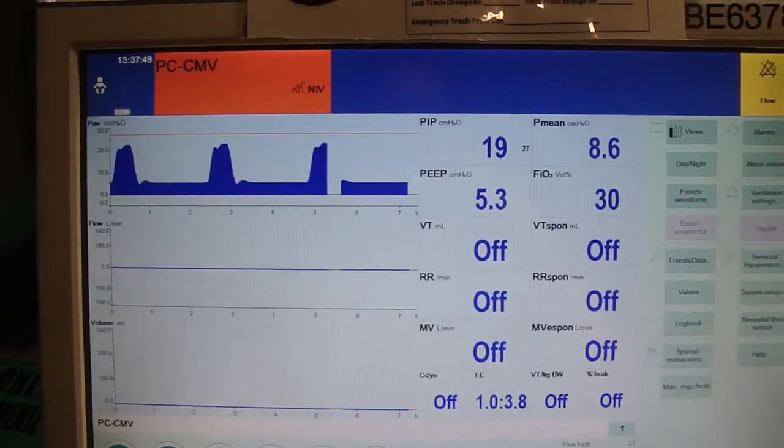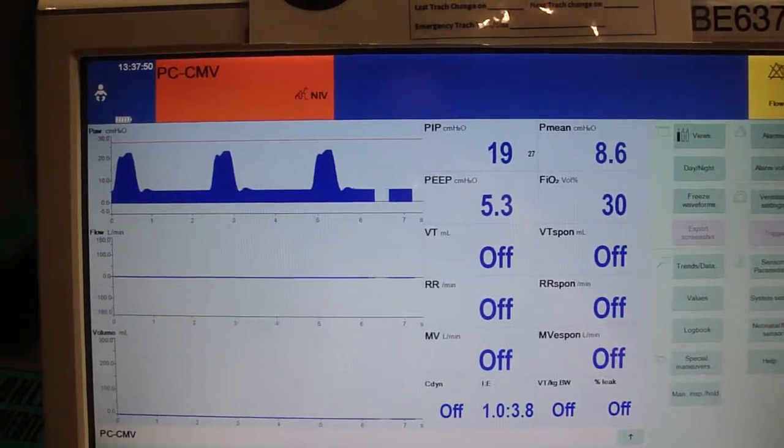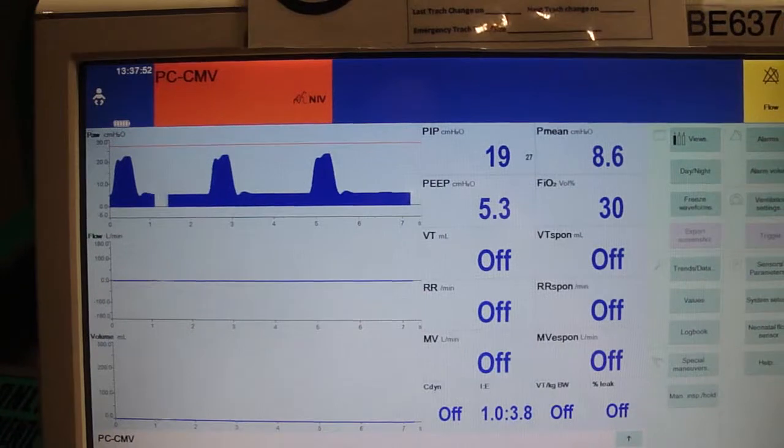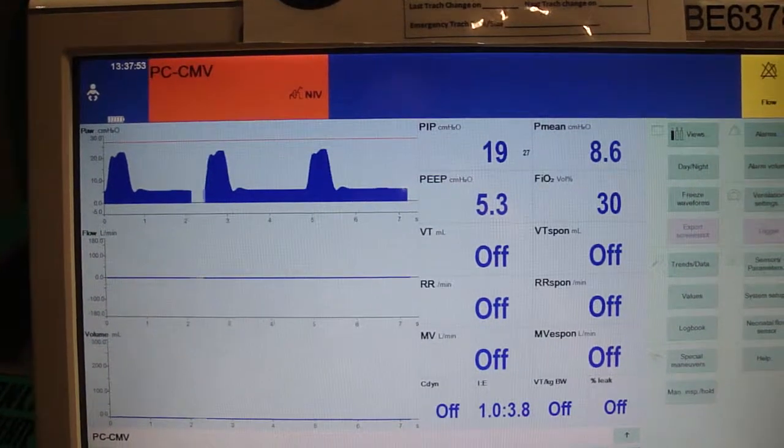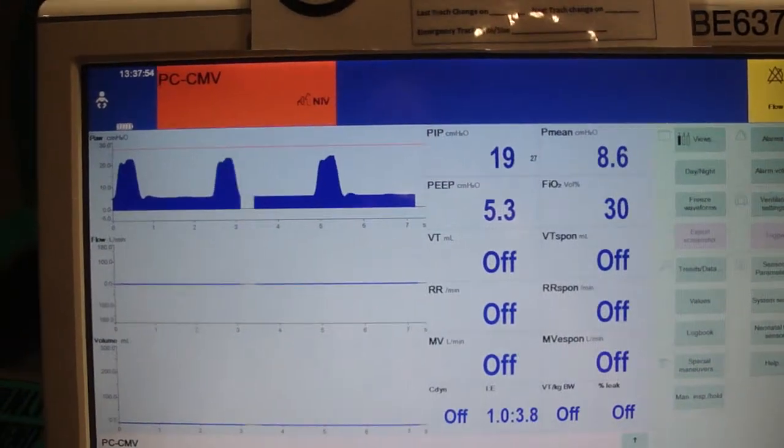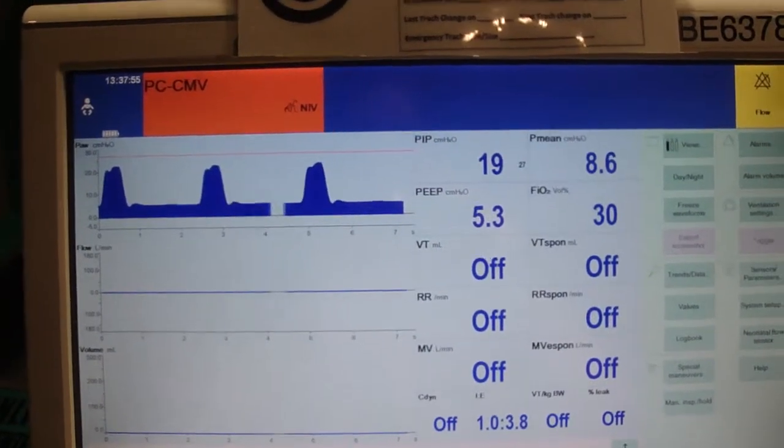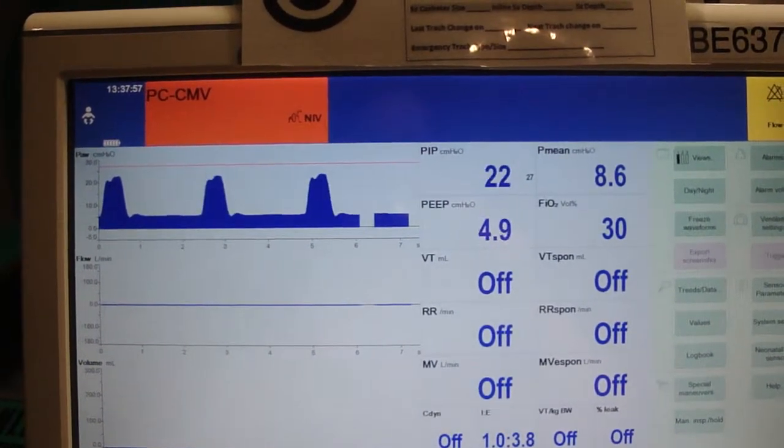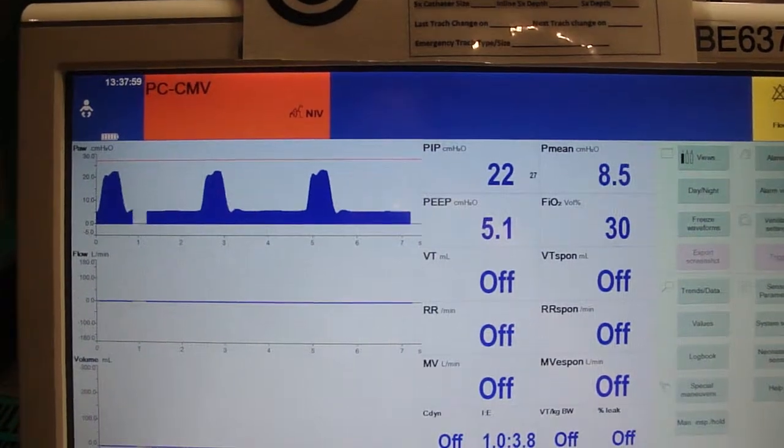You'll get a disconnect alarm. There are no flow measurements as there is no flow sensor in line. So this is a step between CPAP and intubated ventilation.